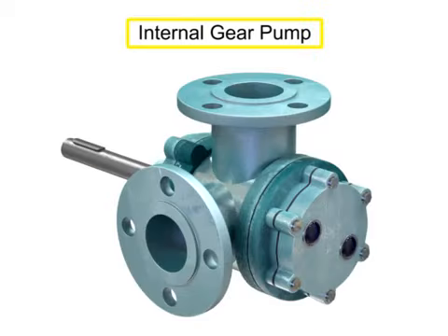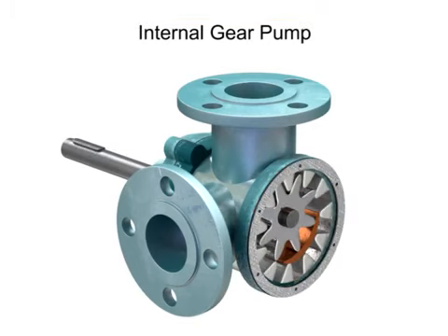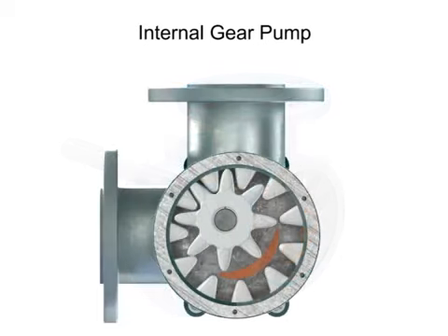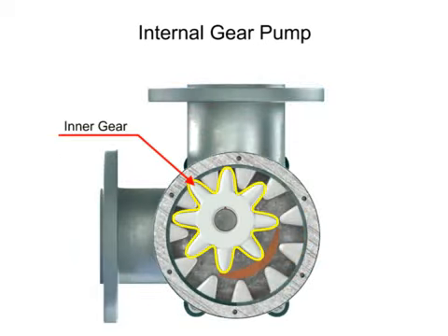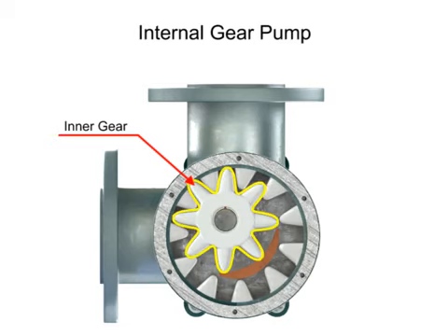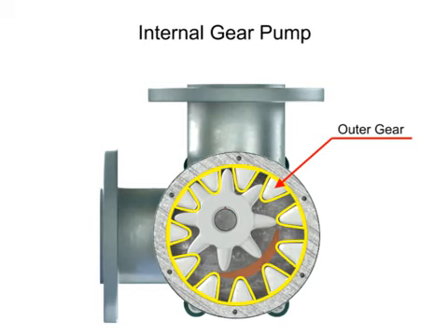Internal gear pumps are exceptionally versatile. This type of pump has one inner gear inside a second outer gear. The inner gear has a shaft driven by a motor and has teeth that protrude outward, while the outer gear has teeth that protrude inward toward the center of the pump.